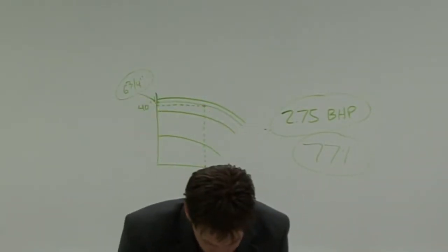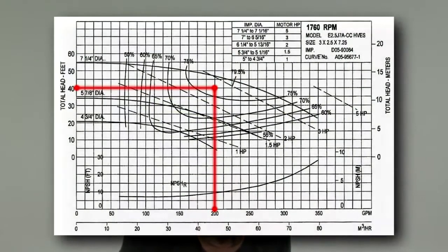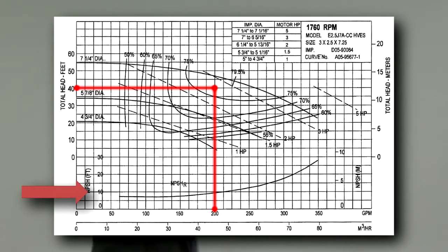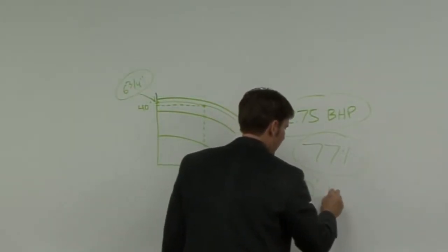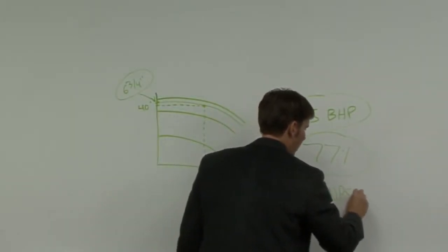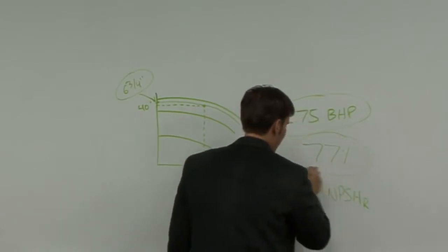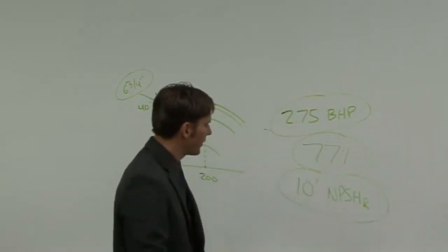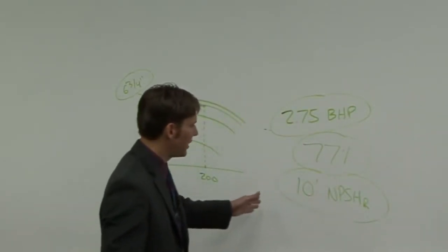And then last but not least, on this pump curve, we could look at our NPSHR, and we are sitting there real close to that 10 feet. Let's just say that we need 10 feet required, 10 feet of NPSHR. Now, to really make this NPSHR work for us, we would have to calculate our NPSHA.